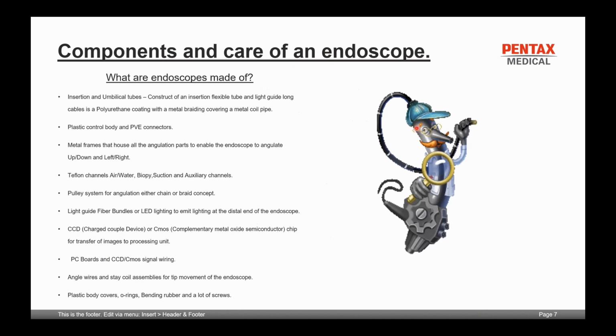So it does have quite a robust outer casing of the endoscope to sort of protect all your components internally, especially your fiber bundles, which are quite fragile. You've got a plastic control body and PVE connectors. You've got metal frames that house all the angulation parts to enable the endoscope to angulate up, down, left, and right. You've got channels within your endoscope, air, water, biopsy, suction, and auxiliary jet channels, and that's all manufactured out of a Teflon.